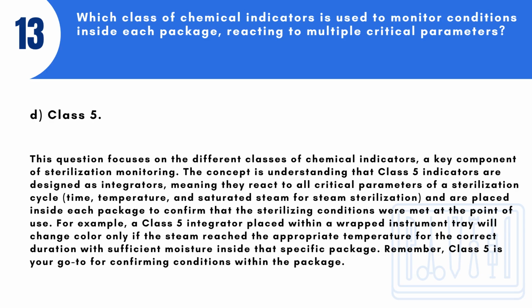Answer: D. Class 5. This question focuses on the different classes of chemical indicators, a key component of sterilization monitoring. The concept is understanding that Class 5 indicators are designed as integrators, meaning they react to all critical parameters of a sterilization cycle, time, temperature, and saturated steam for steam sterilization, and are placed inside each package to confirm that the sterilizing conditions were met at the point of use.